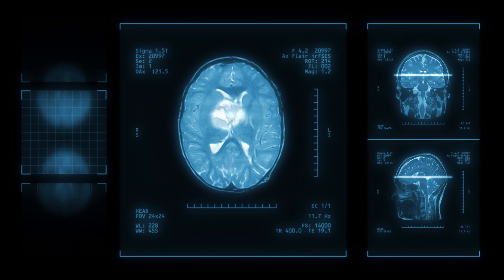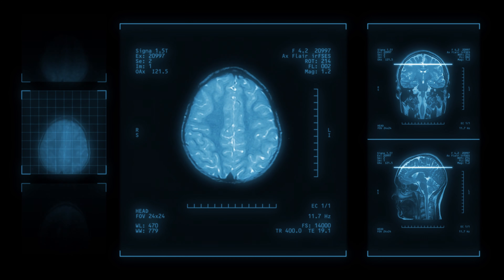Designing these headphones in collaboration with Odyssey, the fidelity of the headphones was a critical factor. The challenge was to use technology that can work inside of the coil and not create image issues. What we've ended up with is a scanner-agnostic headset — you can put this into any scanner, any make, any power, and it's going to give you the same noise cancellation performance.